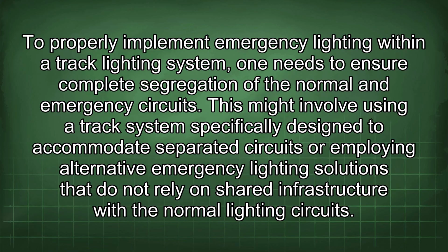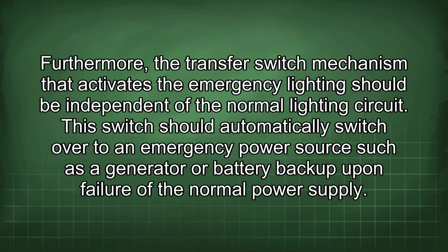To properly implement emergency lighting within a track lighting system, one needs to ensure complete segregation of the normal and emergency circuits. This might involve using a track system specifically designed to accommodate separated circuits or employing alternative emergency lighting solutions that do not rely on shared infrastructure with normal lighting circuits. Furthermore, the transfer switch mechanism that activates the emergency lighting should be independent of the normal lighting circuit. This switch should automatically switch over to an emergency power source such as a generator or battery backup upon failure of the normal power supply.